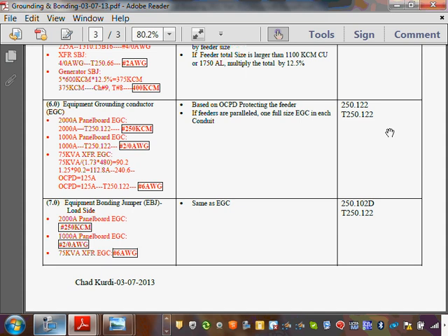Okay, so that's your set. What's the logic that you have to have a full size equipment grounding conductor in every set? Well, because when you pull the equipment grounding conductor in every set, if you have a ground fault in any set, they want the equipment grounding conductor to be able to handle the largest ground fault imposed on the system with every set. Because we're sizing it based on the system. That 1,000 amp. See, we size based on what? The 1,000 amp, not on the conductors inside the pipe. So they want that 2/0 to handle the ground fault that could be generated by a 1,000 amp circuit breaker, as high as that could be, in every set.